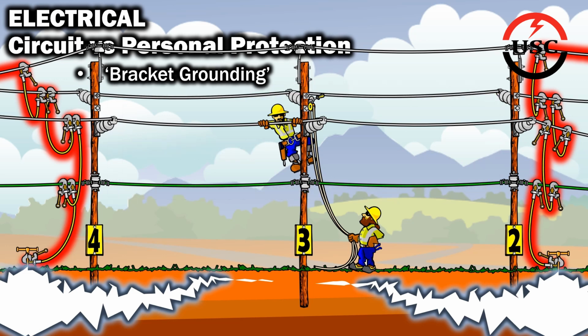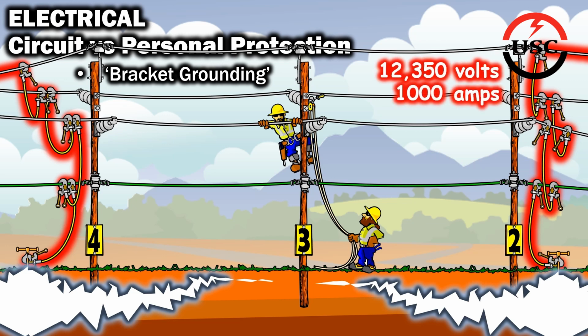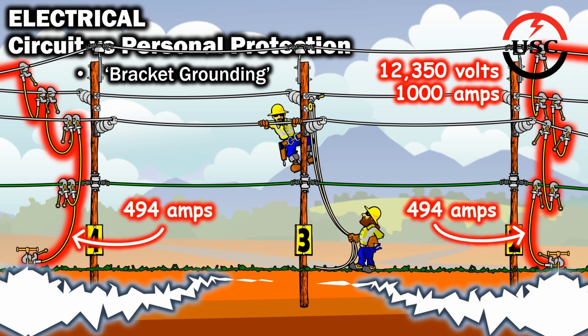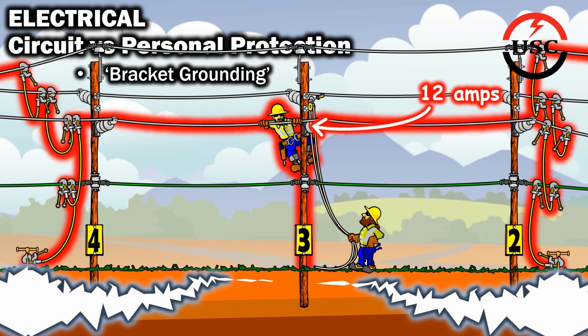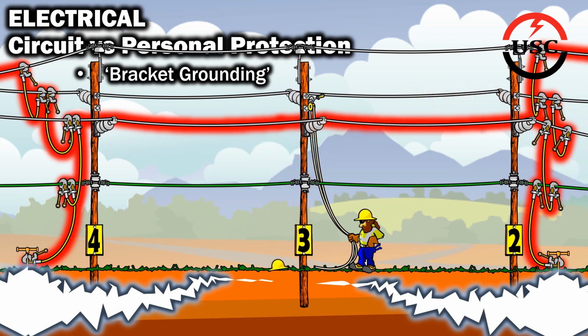This bracket grounding scenario was recreated under controlled conditions to find out just what would happen in such an instance. The controlled experiment induced a fault of 12,350 volts and 1,000 amps of current on the line. The results showed each set of grounds channeling 494 amps away from the worker. But the worker was still exposed to 12 amps of fault current. So, pop goes the meat fuse.